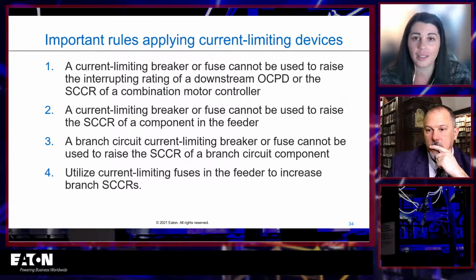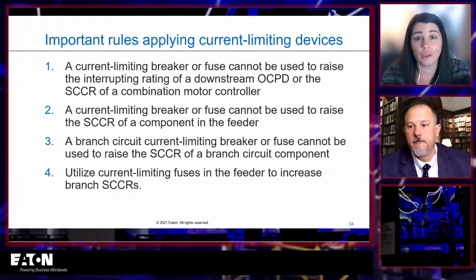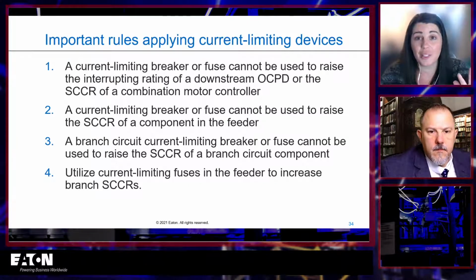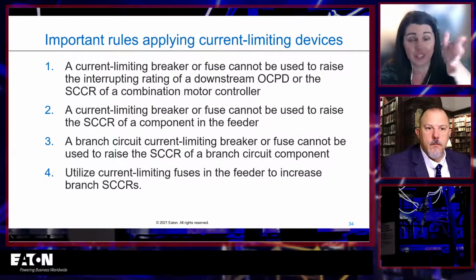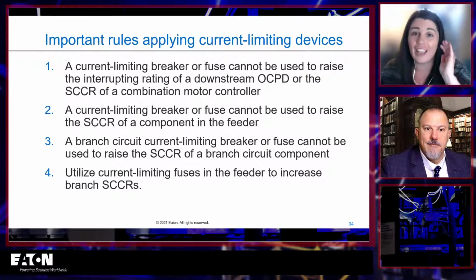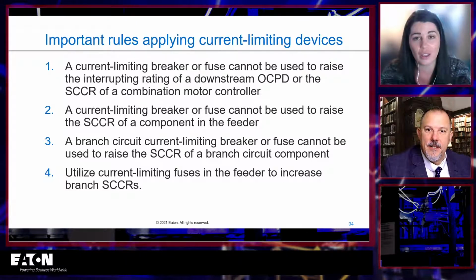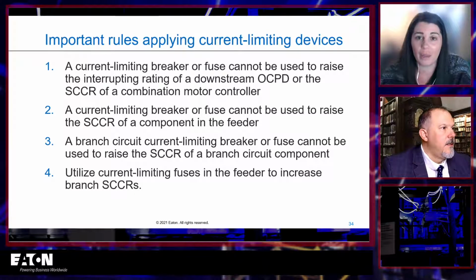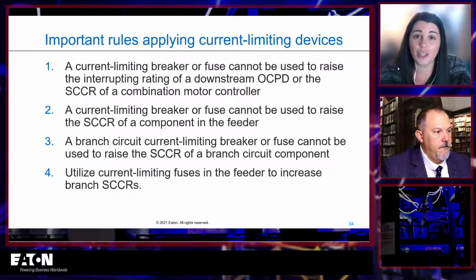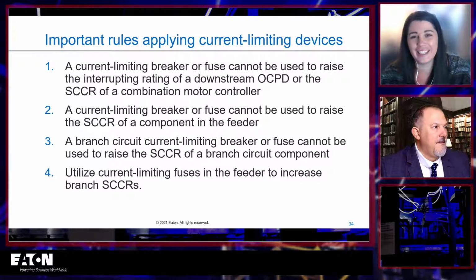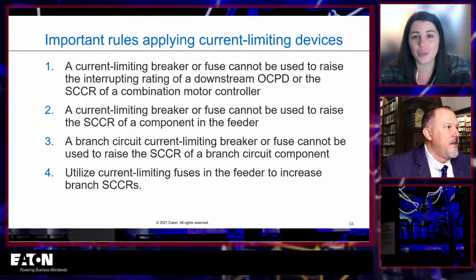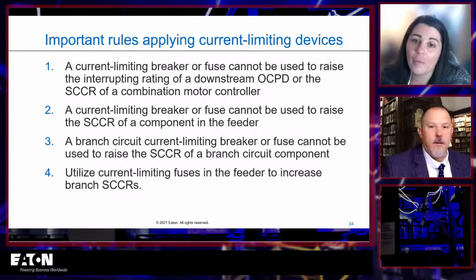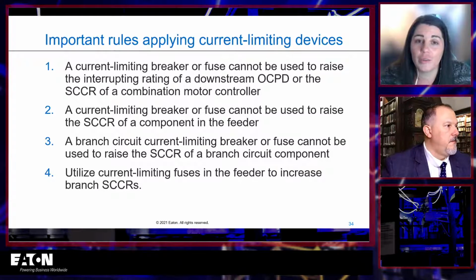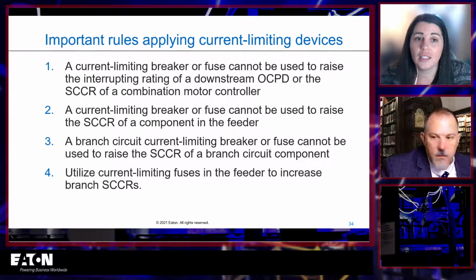So again, I have a love-hate relationship with this specific step in determining short circuit current rating, because it can be very, very useful in certain circumstances, but these rules are also often broken and they should not be. It's really, really important that we don't break these rules when we're determining the short circuit current rating of my panel. So it's one of those exercise with caution. Make sure you are following all the rules when you're doing this.